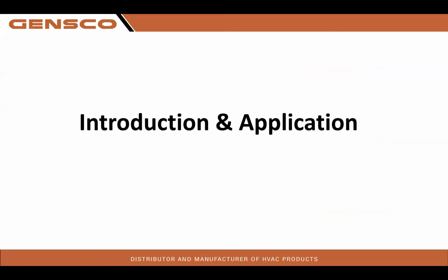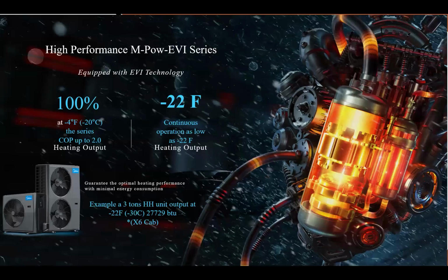Introduction and applications. Let's talk a little bit about this equipment. It is extremely low temp, great performance. Price point to performance is hard to beat, okay? On a 3-ton hyperheat, we've got 100% capacity at -4 degrees with a COP of up to 2.0, and continuous operation as low as -22 degrees.